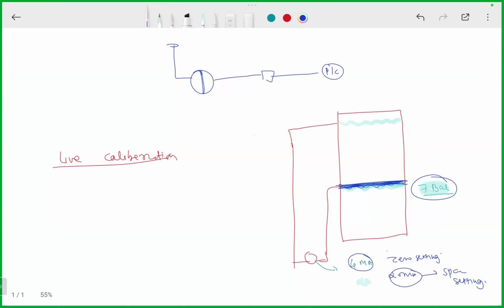Okay, sir. Set 4 milliamp. Output signal should be 4 milliamp. If it is not, adjust the zero setting. Then increase the water level to the highest point. And then output signal should be 20 milliamp. If it is not, adjust your span setting. So this is your practical approach.